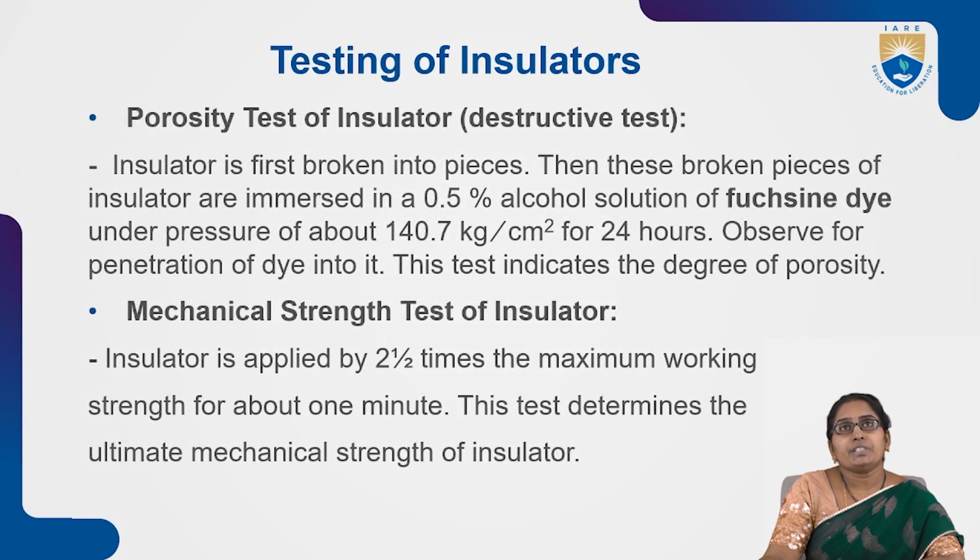Next, porosity test of insulator. What they do is the insulator is first broken into pieces, and then these broken pieces are immersed in a 0.5% alcoholic solution of fuchsine dye under pressure.